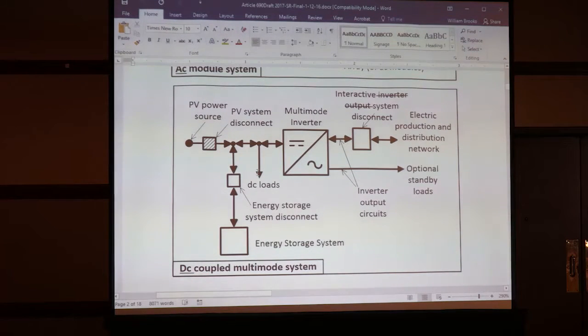DC load circuits have historically been treated as part of a PV system. What a craziness. We just did what we did because we had to. Those used to be part of a PV system, and they were considered as part of the PV system. Receptacles, hardwired systems, the whole thing. Craziness. They're not part of a PV system. They're loads. The code has all kinds of rules about loads, and they have nothing to do with PV. So that's it, and then we could have a multimode inverter.